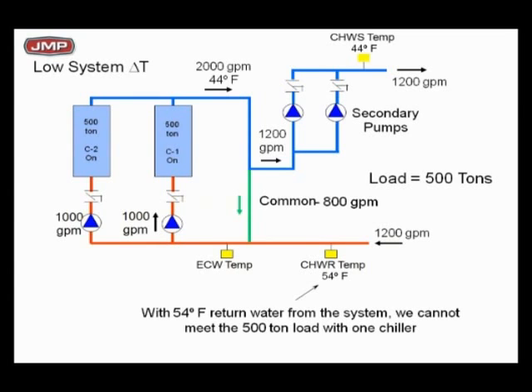Same setup as before. I've got two chillers running, 2,000 GPM, 44 degree water being produced. I'm going out at 1,200 GPM at 44 degrees. I'm coming back 1,200 GPM at 54, not 56. We cannot meet the 500-ton load with one chiller. Slow down and take a look. Do the BTUs in your mind. I know we're in a hurry, as always, but load is 500 tons. I'm having to run 1,000 tons worth of chillers. I'm having to run two 500-ton chillers to give you 500 tons because you have low delta T syndrome.